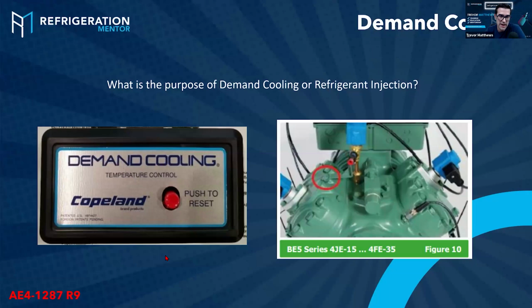Here in Canada, where I'm at, since 2016, so almost 10 years now, they've been doing retrofits from 404 and R22 to 448, 449. Back in the 80s, the 90s and the early 2000s, when I worked in supermarkets in the field on the tools, I worked on tons of low temp R22. All of those R22 low temp systems had a fan on the top, and they had one of these demand cooling modules. There was a lot of Copeland in Canada at the time. It was dominating Western Canada for sure. I've seen some Bitzers. There's way more Bitzers out there now than there was back when I was working on the racks. I worked on a lot of different ones, but we always had this demand cooling.